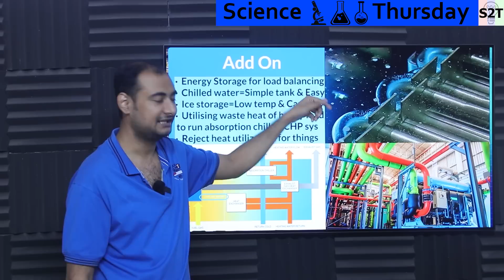That's why ice takes so long to make, it's not the energy part, we can leach that much energy no problem, it just takes so long to transmit the energy through ice. Liquid is a super good conductor, but the ice layer is a good insulator, which makes your life harder. This takes a lot of compressor load, meaning if you want an ice system, your chiller units, the compressor parts, will be under a bit of stress load.